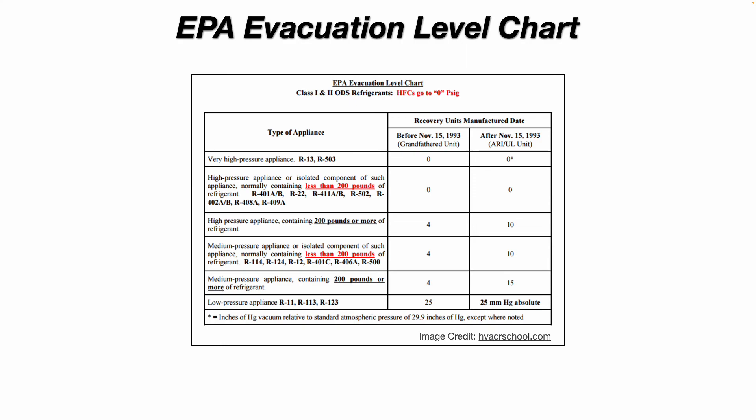The EPA evacuation level chart — from HVACRSchool.com, a great source of information and training. You need to memorize this chart. Pay particular attention to the evacuation levels for high-pressure appliances containing less than 200 pounds versus 200 pounds or more. The inches of vacuum required differ depending on whether the appliance has more or less than 200 pounds, and whether the recovery unit was manufactured before or after 1993.